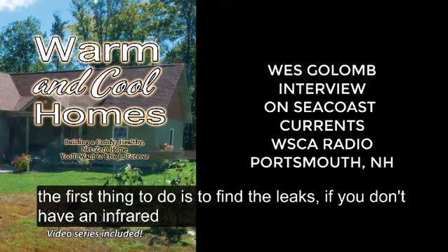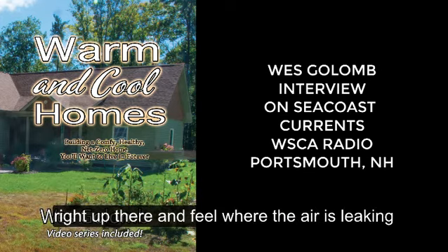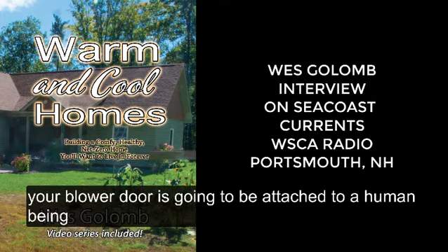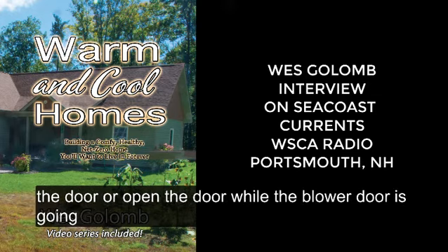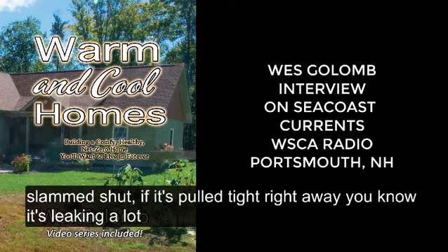If you don't have an infrared camera, actually the best way to do it is to get your hands right up there and feel where the air is leaking. You start with a room, and you have the blower door going, and usually your blower door is going to be operated by a human being who's been trained in this. But if somehow you're doing it yourself, you would maybe go to a room and close the door, or open the door while the blower door is going, and feel how much it gets slammed shut. If it's pulled tight right away, it's leaking a lot.